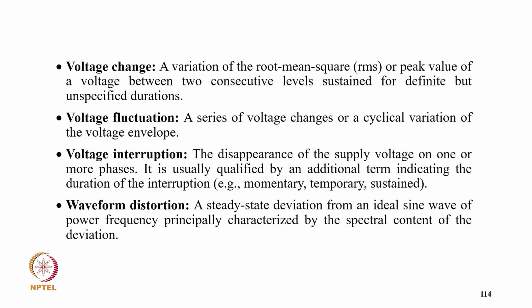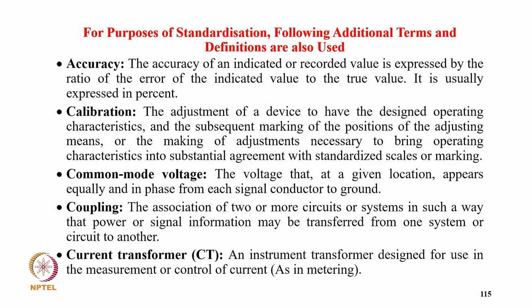Waveform distortion, a steady-state deviation from an ideal sine wave of power frequency, principally characterized by the spectral content of the deviation. Now, for the purpose of standardization, the following additional term definitions are also used. Accuracy: the accuracy of an indicated or recorded value is expressed by the ratio of the error of the indicated value to the true value, usually expressed in percent. Calibration: the adjustment of a device to have its designed operating characteristic, and the subsequent marking of the position of the adjusting means or making the adjustment necessary to bring the operating characteristic into substantial agreement with the standardized scales or markings.